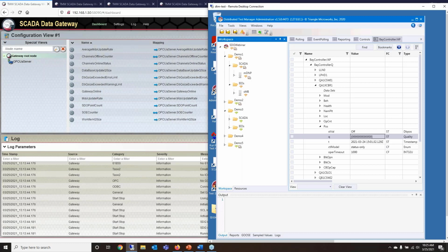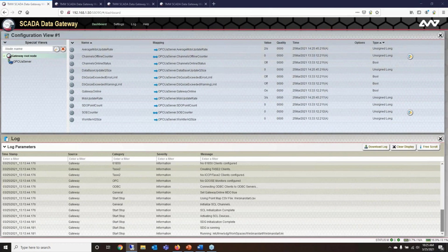In this situation, as mentioned in one of the questions, I'm actually going to be simulating both the IEDs, or downstream devices, and the SCADA, or control center. So based on that diagram we looked at, I have my DNP3 control station and my server Modbus device. That's what I'll be doing for all the demos today. So I'm going to move this off the screen, and I'll put Gateway in the middle. This is our SCADA Data Gateway tool.